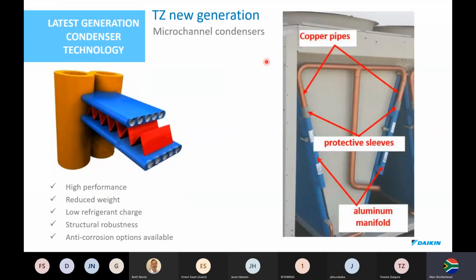Let's have a quick look now at micro channels that we use. These offer very high performance because of the good delta T across aluminium. It's reduced weight. Because it has a great coefficient of heat transfer, we don't need as much refrigerant. Structurally, it is very strong. It's supported in these header tubes, I should say. And anti-corrosion options are available.